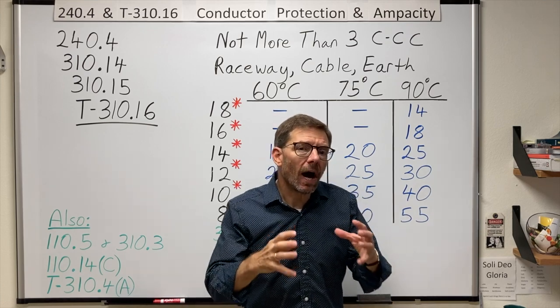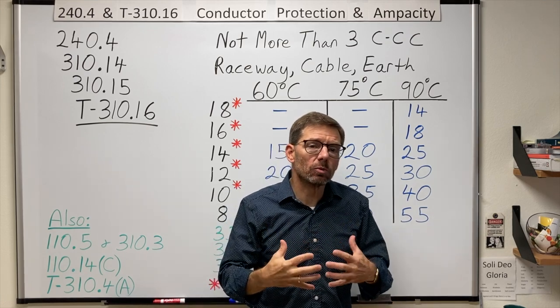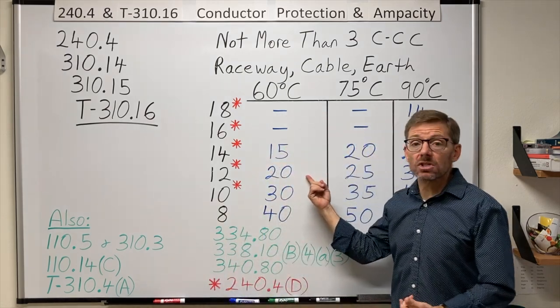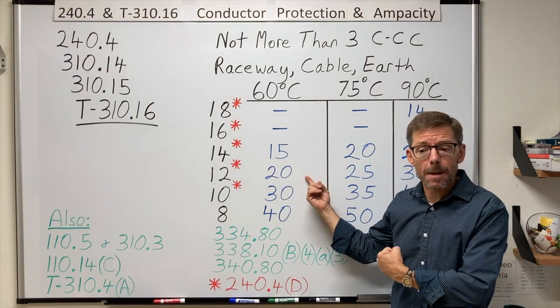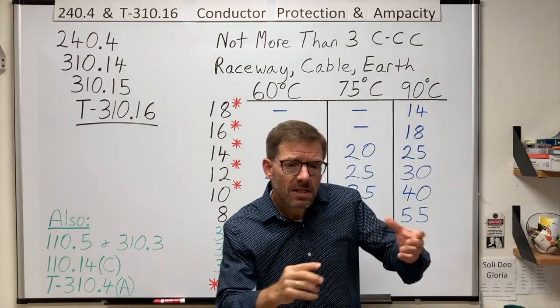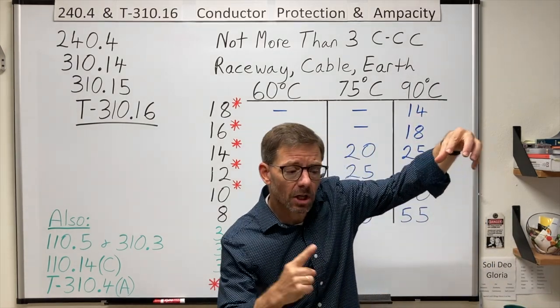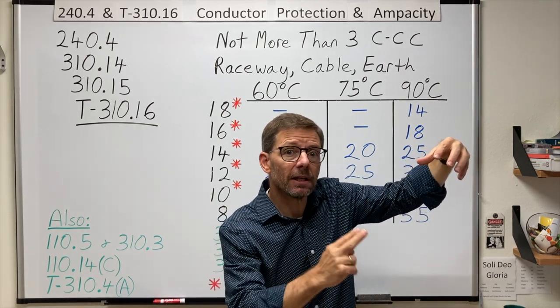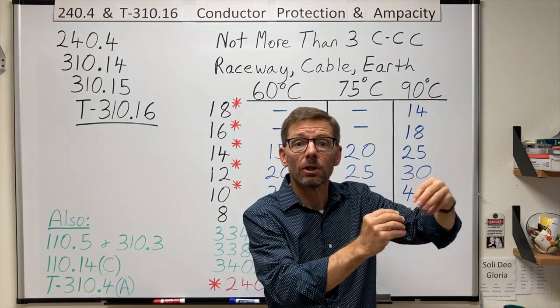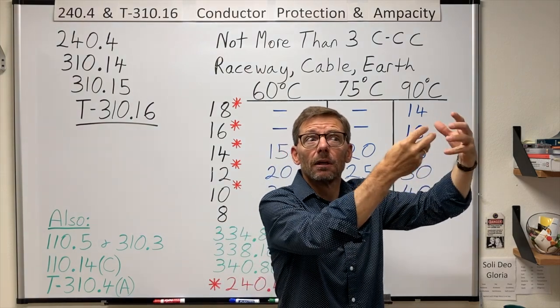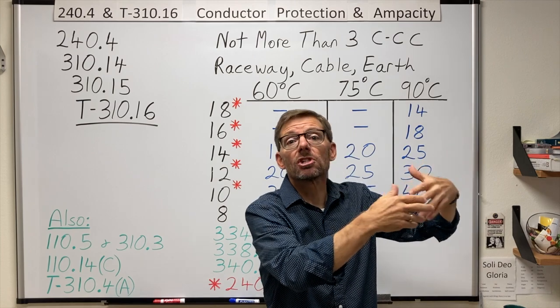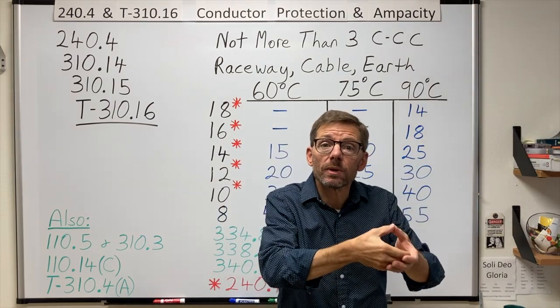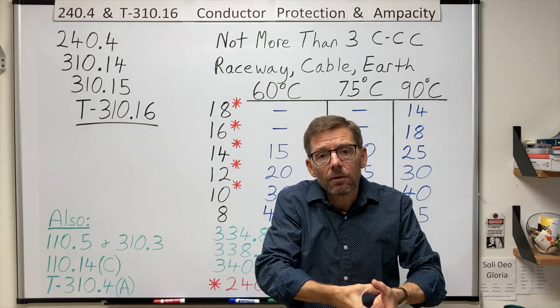So we have to ask, why are we as electricians so concerned with overcurrent protection of equipment, or in this case, specifically conductors? Well, let's consider what happens if I have a conductor and I run increasing amounts of current through it. As the amount of current increases, so does its temperature. It gets hotter and hotter, and it may reach a temperature where it starts to do damage to connected equipment or even to itself, such as breaking down its own insulation.